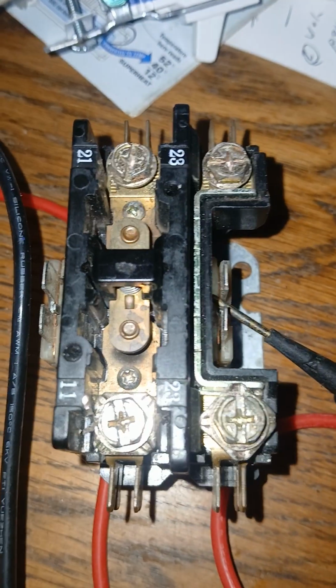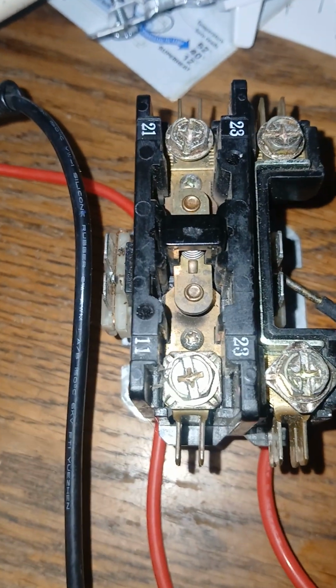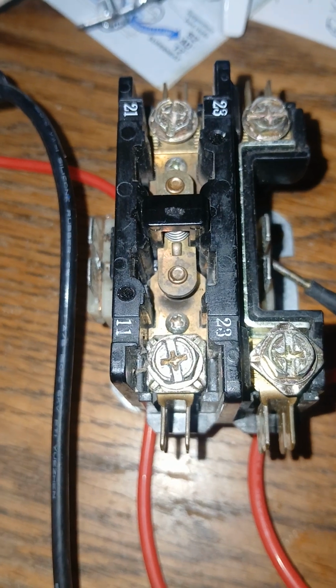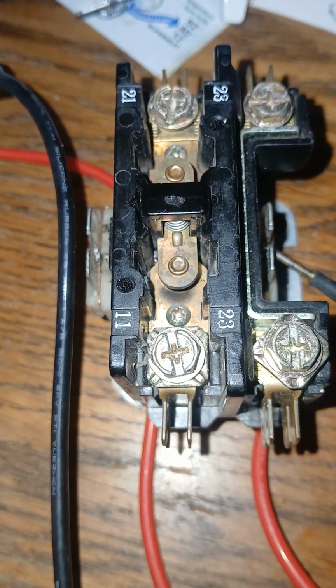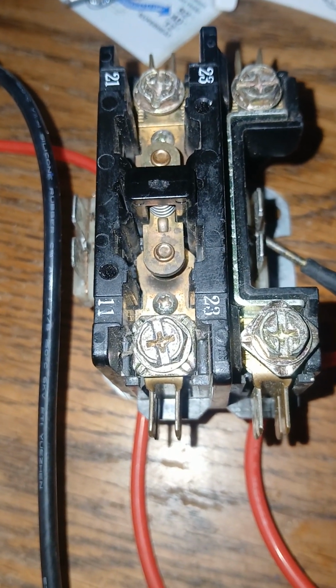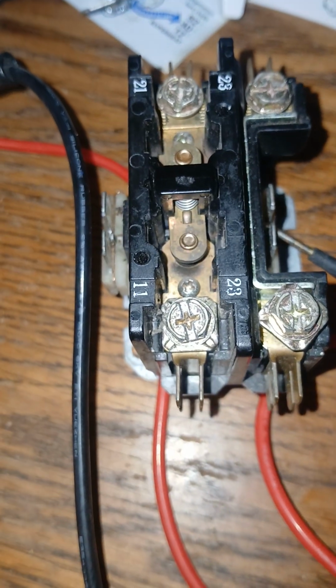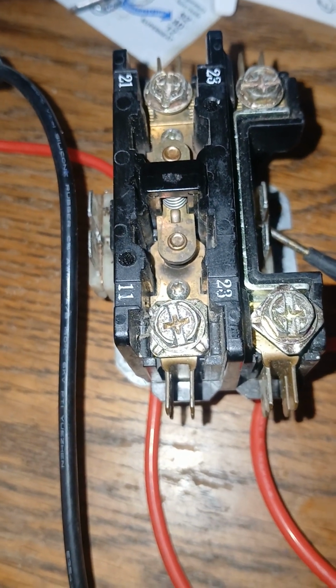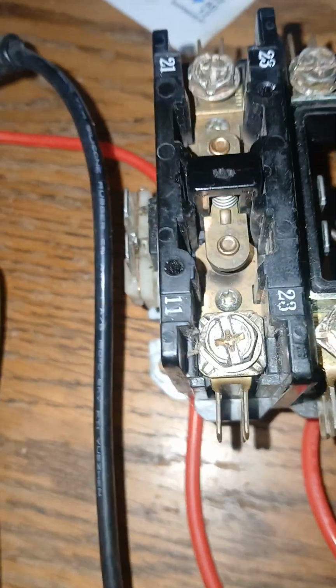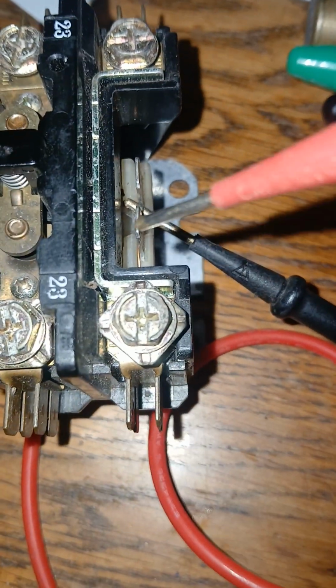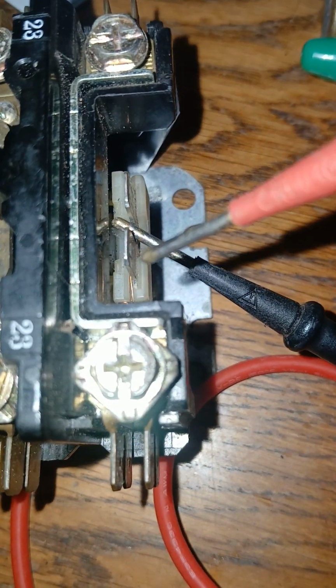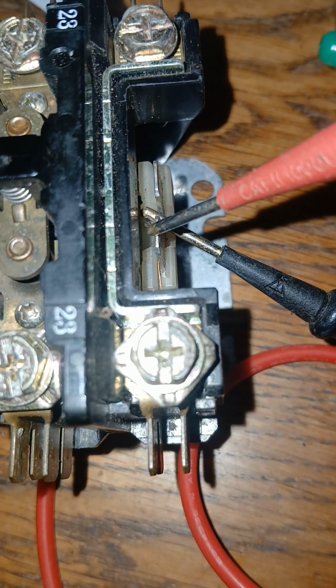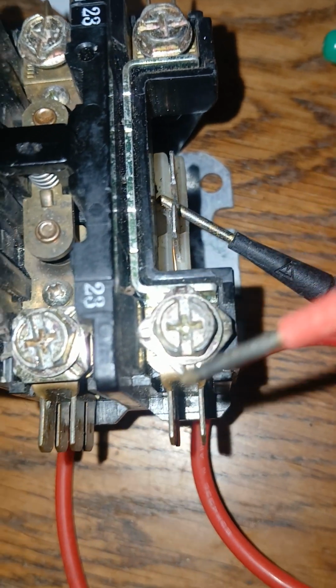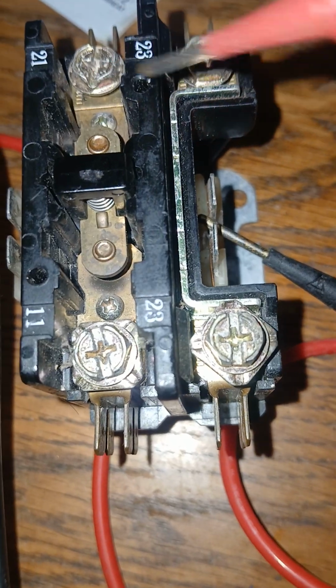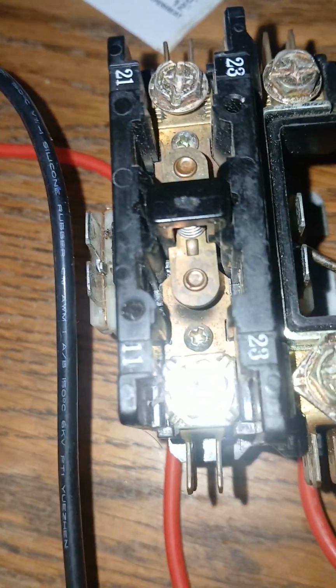So again, it's in the ohms position down here, so 18.3 would be good. Somewhere in the 9 to 20 range may be considered okay. It's hard to say. That's not an exact science, so don't hold me to those numbers. But somewhere in that range of, say, 9, 10 to 20 may be good. See, we have nothing here. We have one probe over here because it's difficult to handle. This is the reason the alligator clips come in handy on the low voltage side. Don't ever use them on the high voltage side because you don't want the shock.